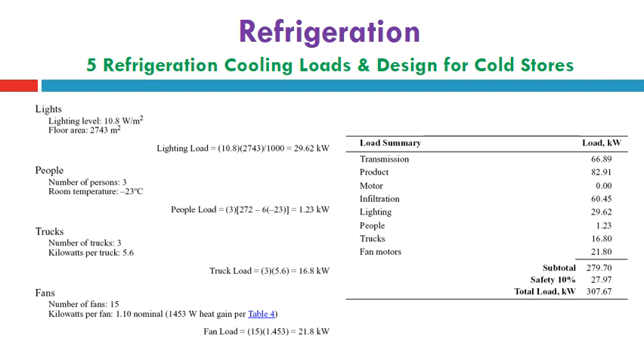All this data is given in the heading of this problem, and can be considered as an example for you to show how we can add the different load components: transmission load, infiltration load, and internal loads with each component: lights, people, trucks, and fans. The number of fans is 15. Kilowatt per fan equals 1.1 nominal, 1453 watt heat gain per table 4. Finally, he can get the total fan load equal to 21.8 kilowatt, and the load summary can be listed here in this table on the right side.